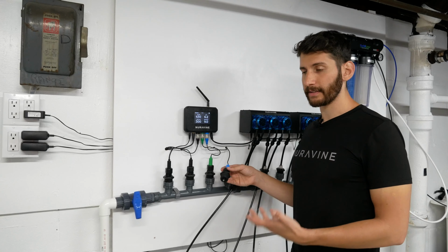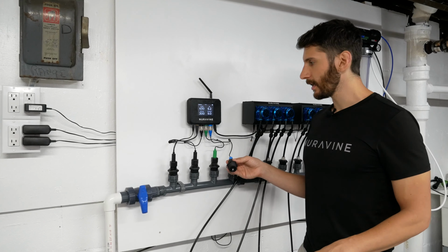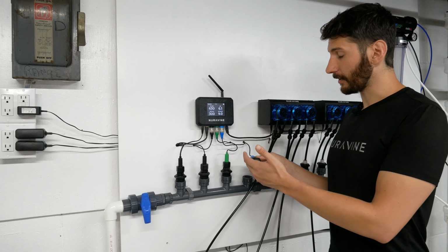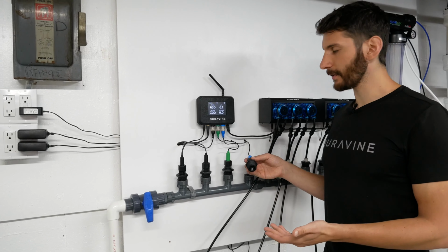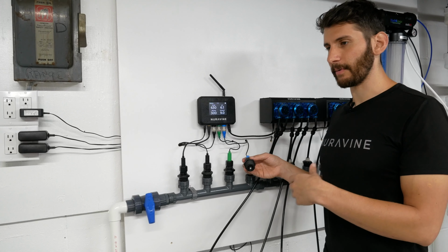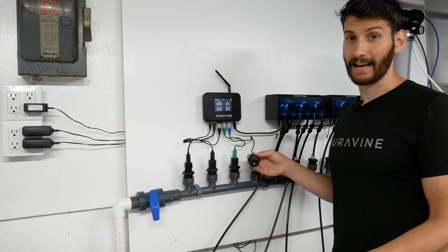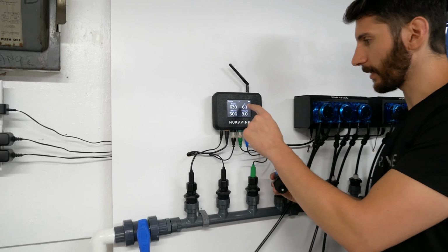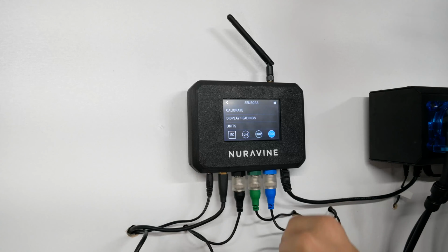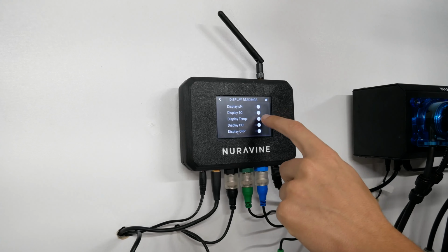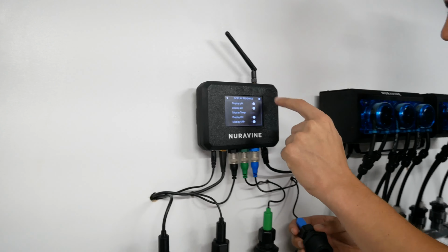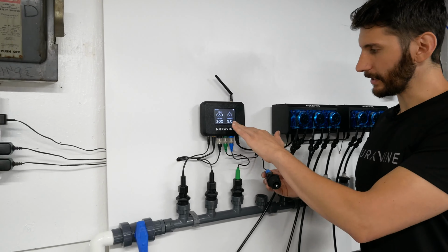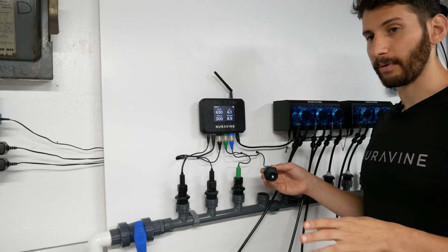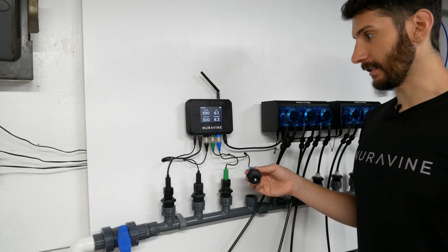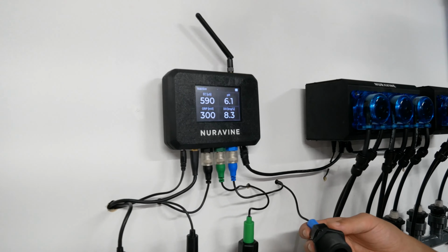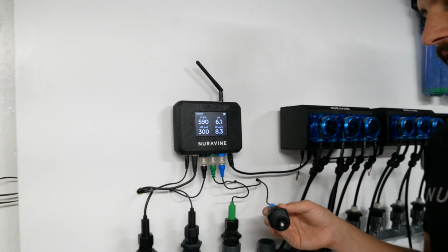So now that we're done calibrating the dissolved oxygen probe, we want to confirm our calibration. Now the value of the dissolved oxygen is going to depend a lot on the temperature. So what we want to actually do is get rid of this temperature so that we can normalize the readings and confirm that we are getting an accurate result. So what I'm going to do here is I'm actually going to go into the menu. I'm going to go to Sensors, click on Display Readings, and then I'm going to get rid of the temperature. Now when we go back to the home screen, we're going to want our dissolved oxygen levels to be somewhere between 8 and 8.4, and that's going to be normal oxygen levels in the atmosphere.